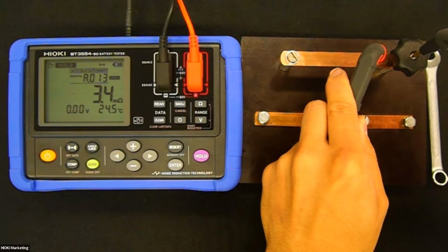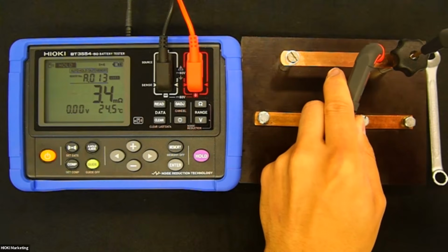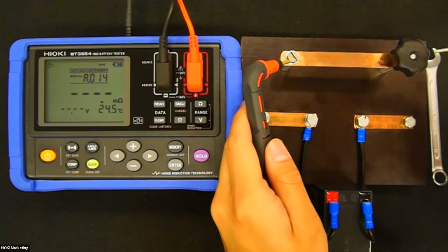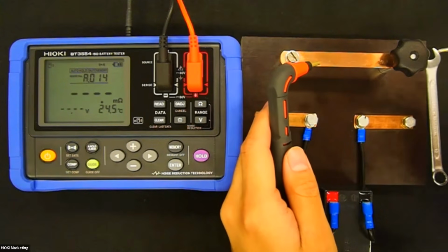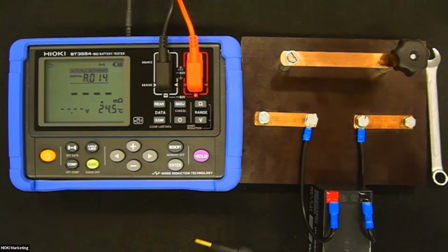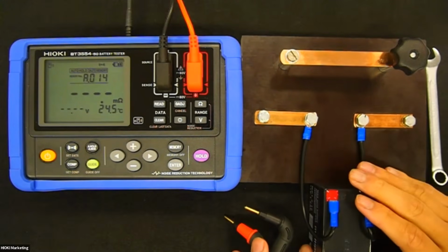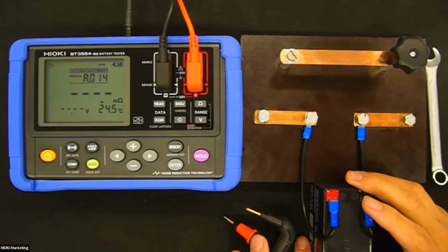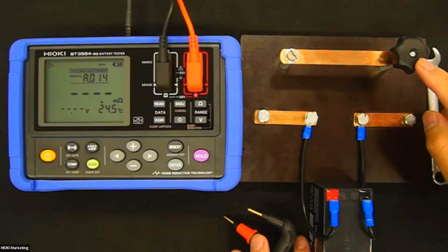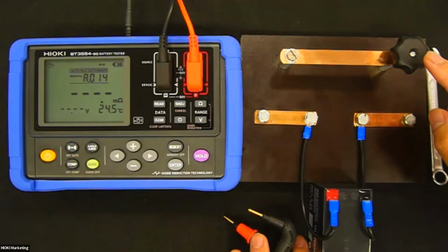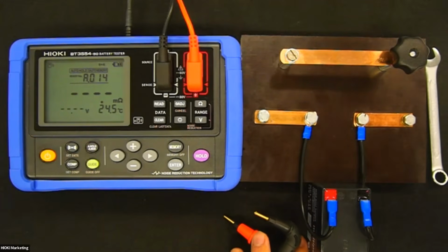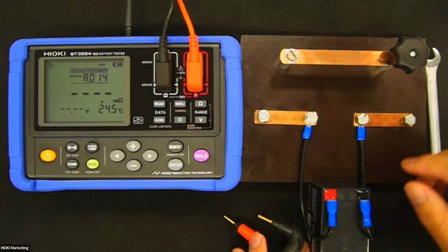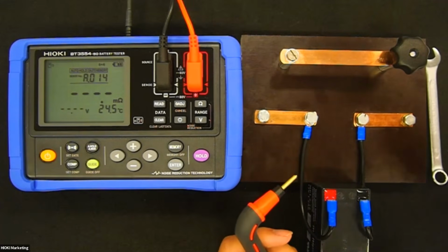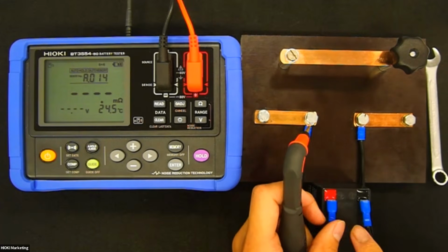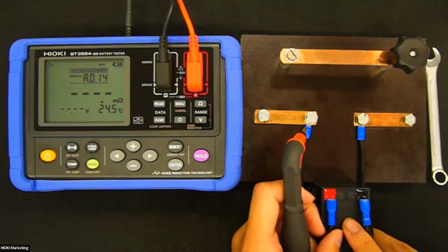Now it shows 3.4 milliohms. As you can see, this board has a different contact resistance. And of course, when you set a threshold for judging the battery test, this board connection resistance affects the measurement result. So please double check the resistance after installing your batteries in the UPS.